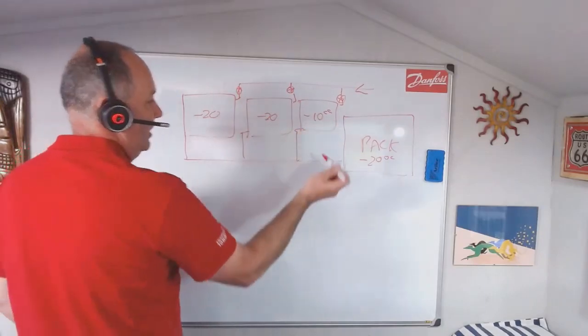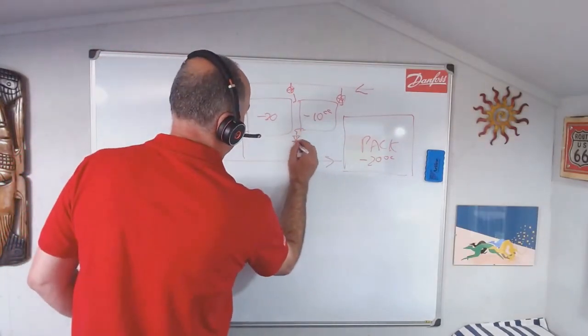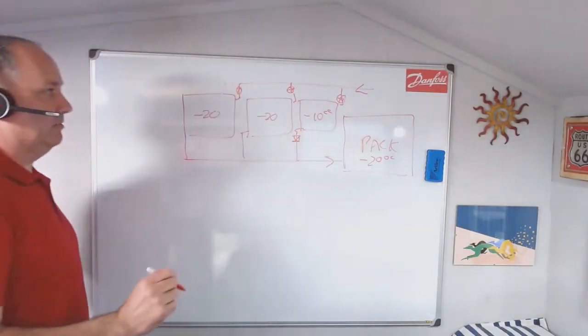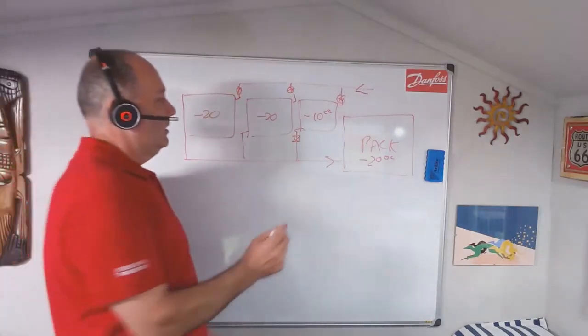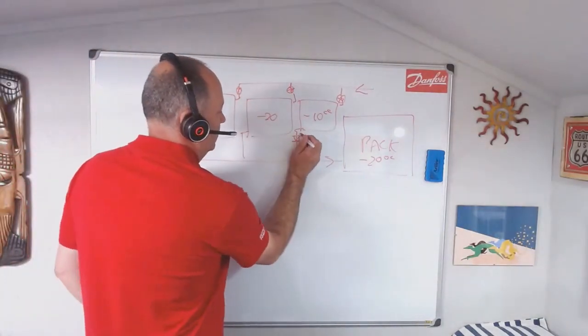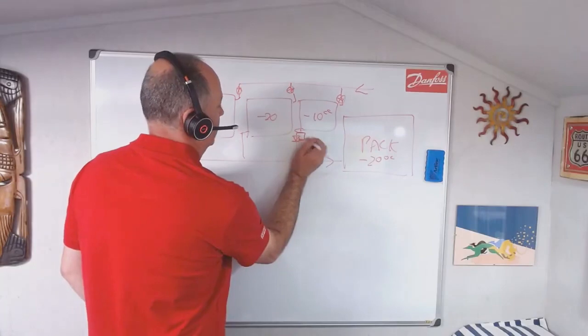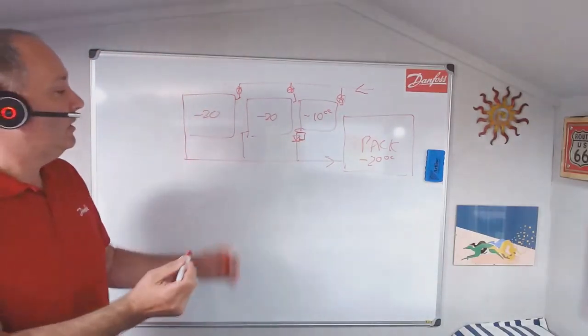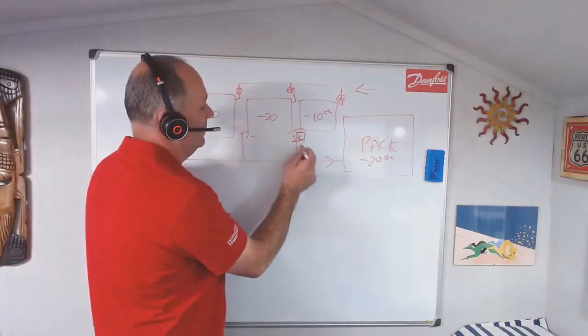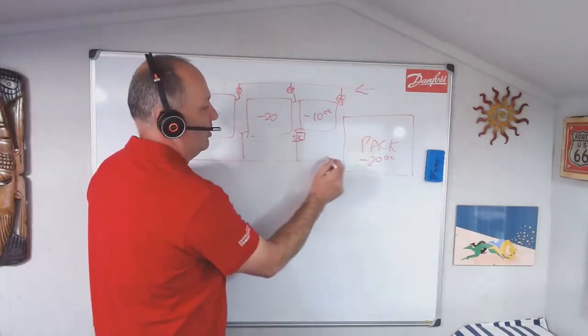If you want that one at minus 10, basically what we do is we put an evaporator pressure regulator valve on the suction line. And basically what that does is it controls that temperature or that pressure temperature relationship. So we basically throttle that suction gas coming back to the pack.